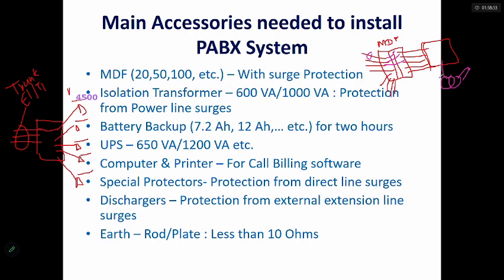One thing is that it has a special voltage requirement, not usually 230. The other thing is that it's very voltage sensitive, so you have to regulate the voltage supply using an isolation transformer.